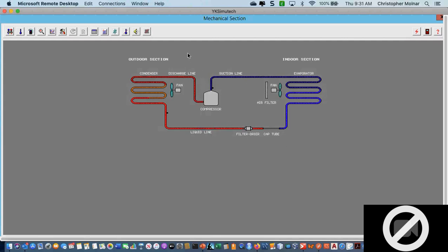We have two sides of the system: high pressure and low pressure. From the compressor, all the way through the condenser, to the metering device, is high pressure. From the metering device — which is like putting your finger over the end of a garden hose and spraying that liquid into more of a vapor or mist pattern — from the metering device all the way back to the compressor is low pressure.